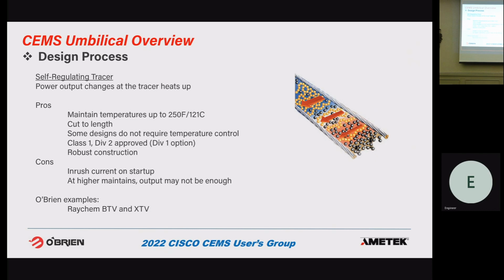But does everybody know how self-regulating tracer works, or at least the basics of it? Because it's kind of a misnomer. A lot of people think, I get a self-regulating tracer in a tubing bundle and I need it to maintain 250F, look it up, and it's going to maintain 250F all year long. It doesn't. What it does is change its power output with temperature. Most self-regulating tracer companies rate their tracers at 50 degrees F or 10 degrees C. So a 20 watt per foot self-reg is putting out 20 watts per foot at 50 degrees F or 10 degrees C. 10 watt per foot, same thing. And as it heats up, it puts out less power. Depending on which tracer you're using, that temperature curve changes. As you go to higher and higher temperature tracers, that output curve gets flatter and flatter.